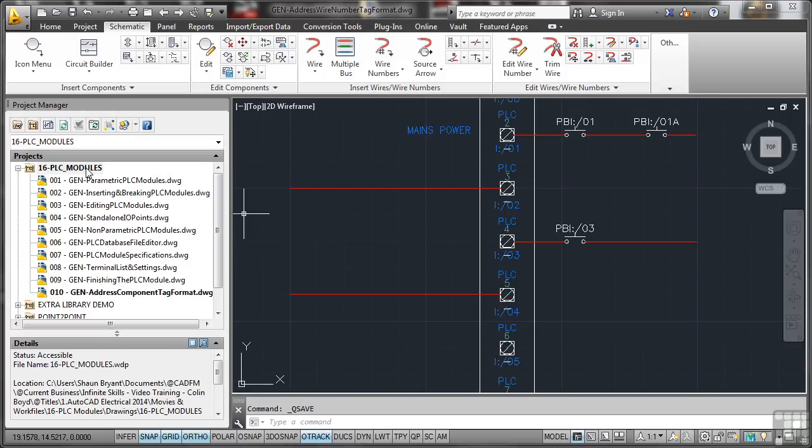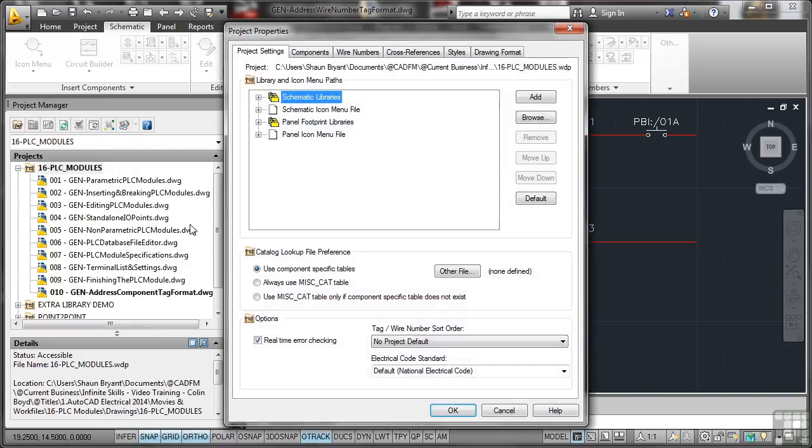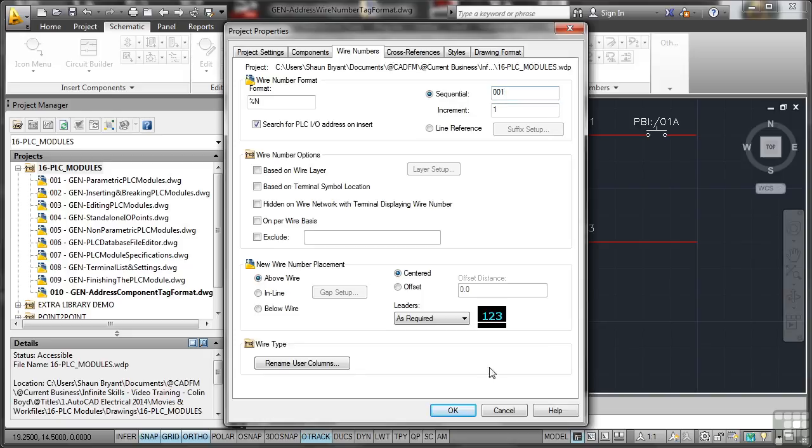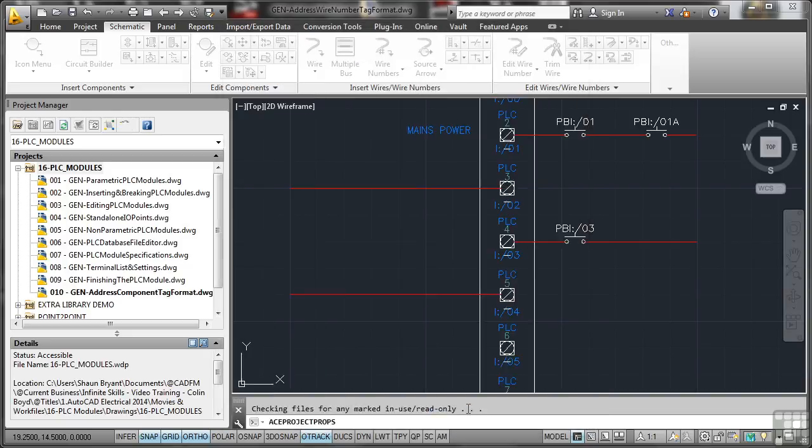We'll go to the project, right click and go to properties. Like we did previously but we're going to look at wire numbering this time. Again we're going to search for the PLC input output address. I'm going to make it sequential. I normally use 001 and I'm going to OK that.